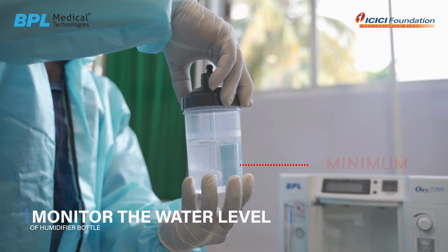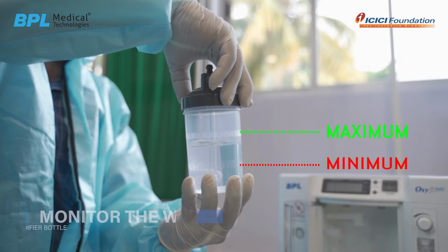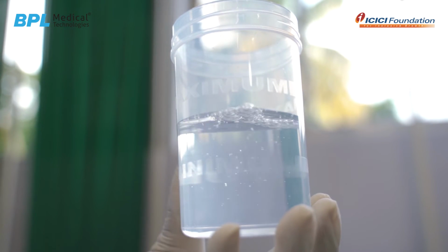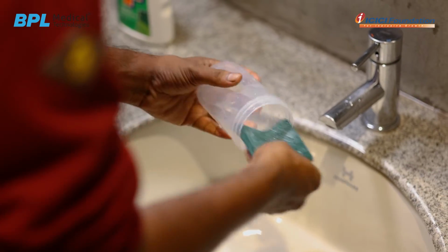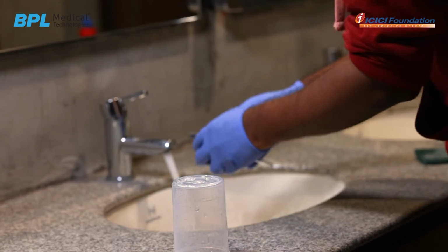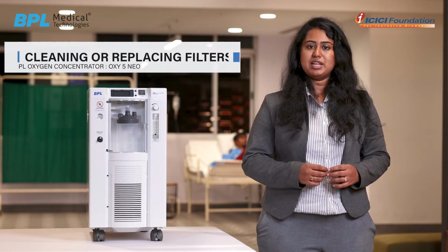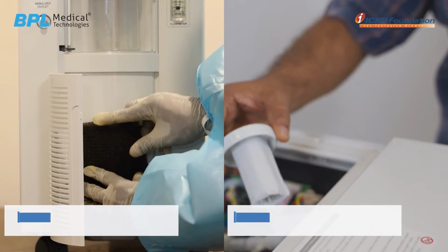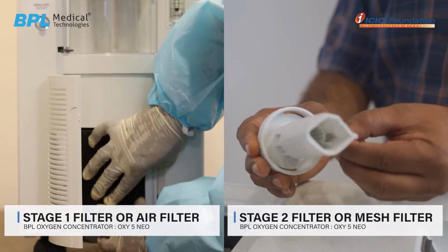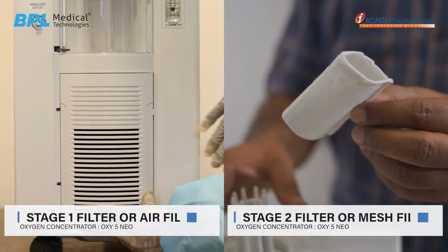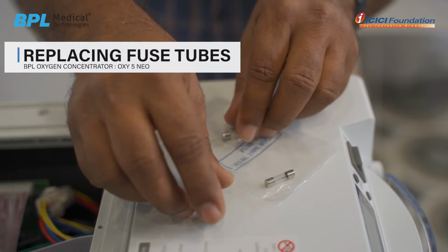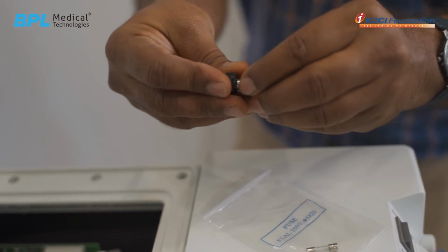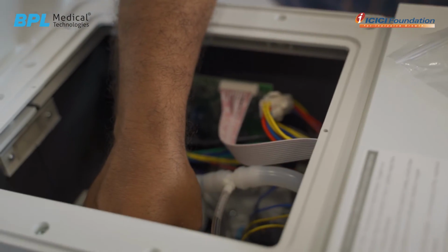Humidifier bottles. User should always monitor the water level in the humidifier. Change the water in the humidifier bottle every day. Clean the humidifier with the liquid detergent and rinse thoroughly with warm water. Cleaning or replacing filters. Oxy 5 Neo has 2 types of filters, stage 1 filter or air filter, stage 2 filter or mesh filter. If the device is used for COVID patients, BPL recommends to change the filters. Replacing fuse tubes. Extra fuses provided as standard. Fuse tubes for net power can be replaced by the user in case of failure.